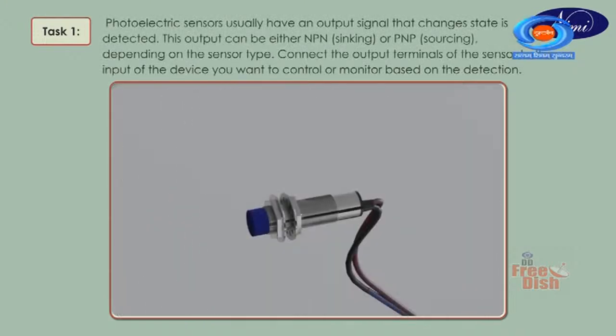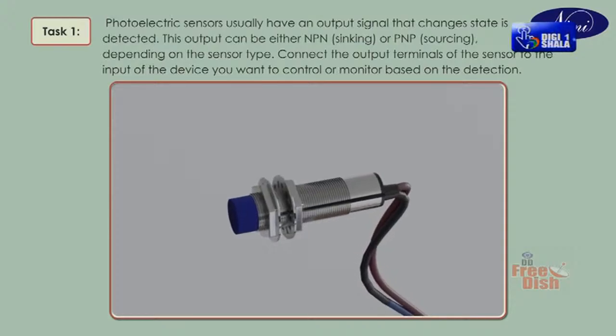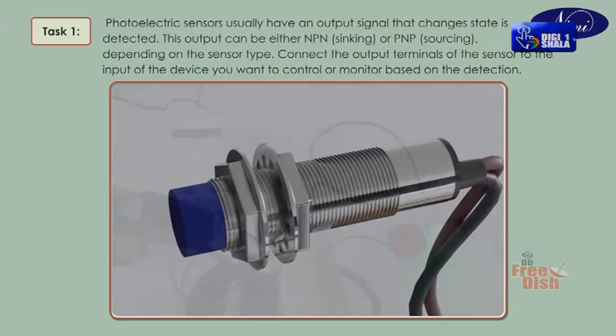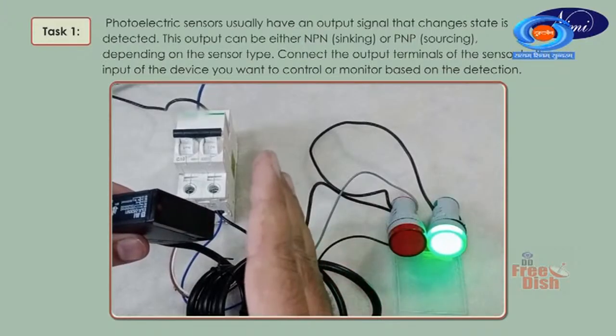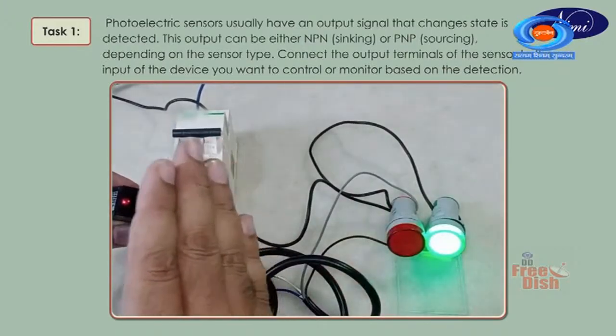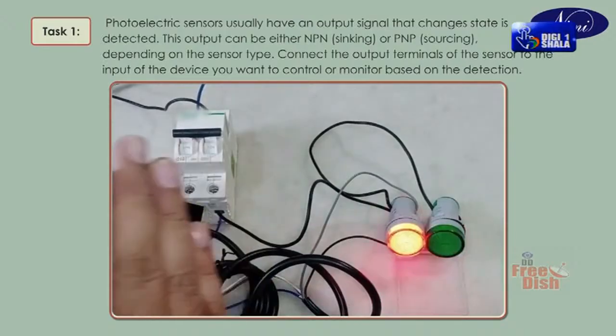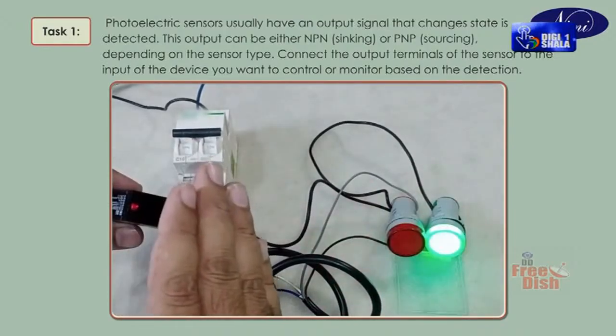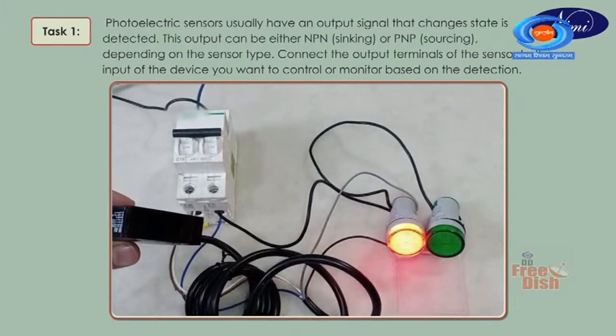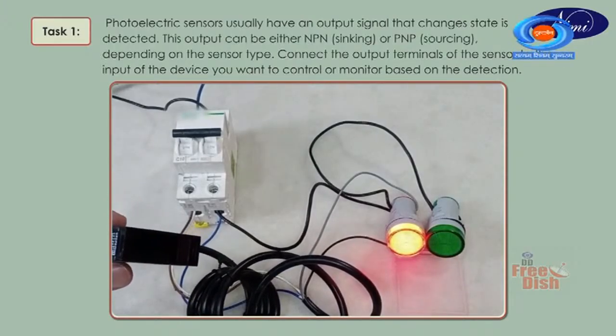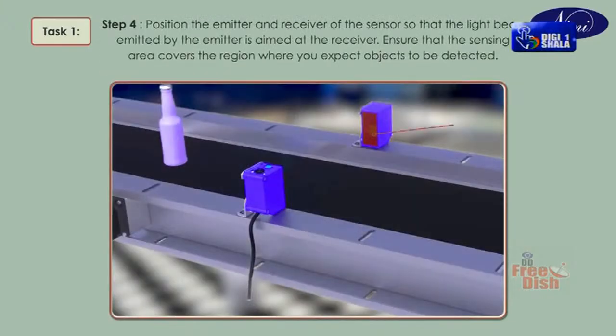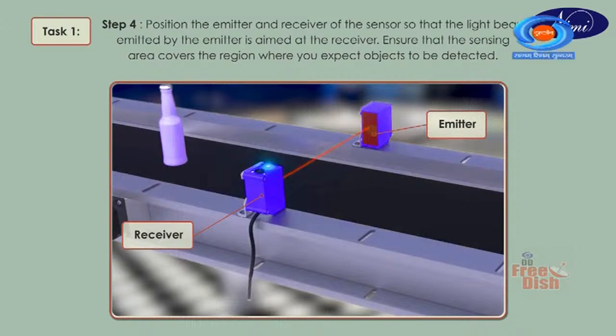Photoelectric sensors usually have an output signal that changes state when an object is detected. This output can be either NPN, sinking, or PNP, sourcing, depending on the sensor type. Connect the output terminals of the sensor to the input of the device you want to control or monitor based on the detection. Step 4. Position the emitter and receiver of the sensor so that the light beam emitted by the emitter is aimed at the receiver. Ensure that the sensing area covers the region where you expect objects to be detected.